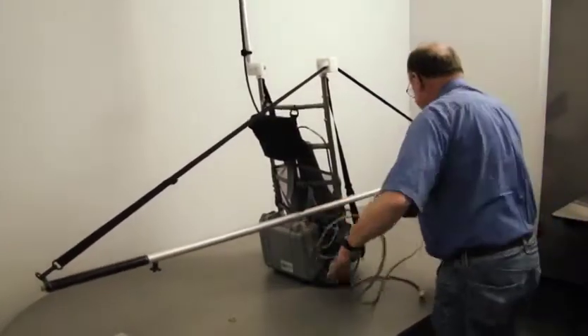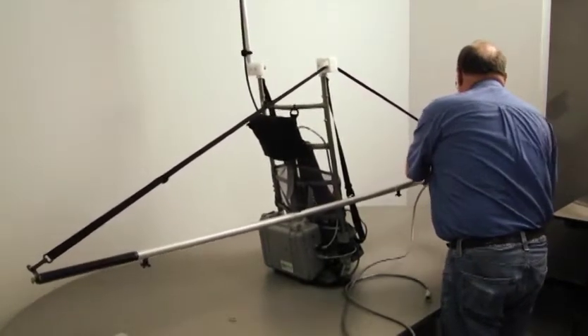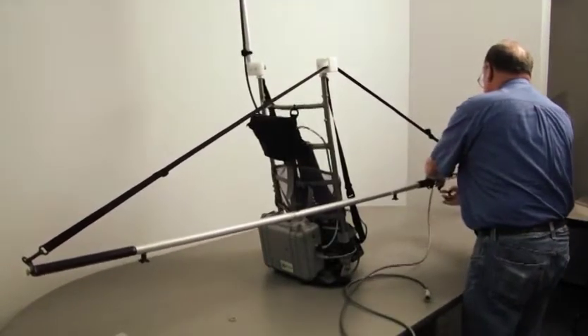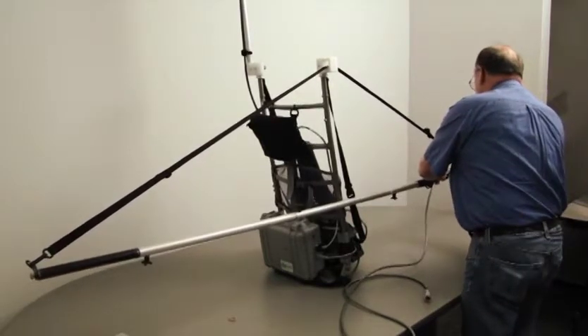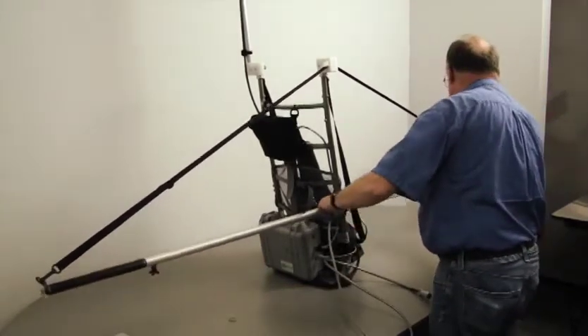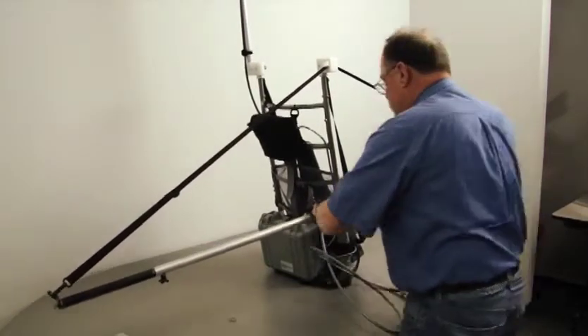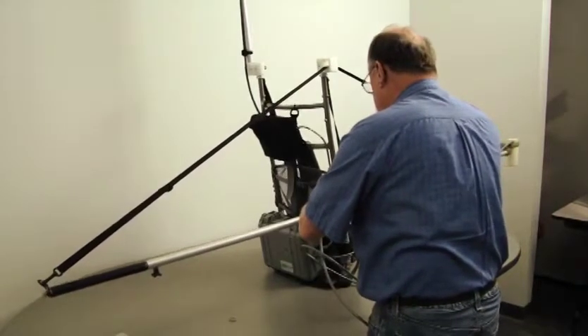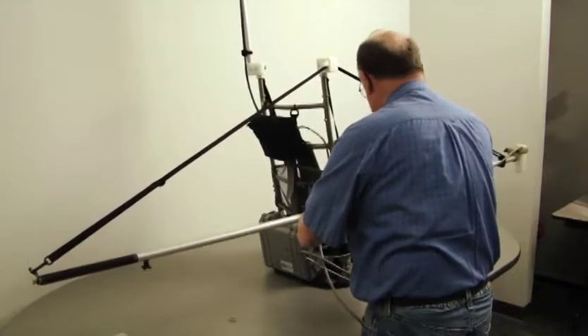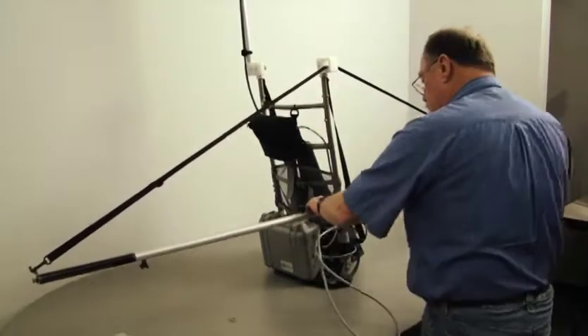The sensor cable gets located with the supplied Velcro strips and cable clamps. I generally just use the Velcro strips, but for long term deployments, you may want to use the cable straps. We want to fit the cable with the supplied mounting materials such that the cable is held close to the staff and it's not likely to get snagged on brush.